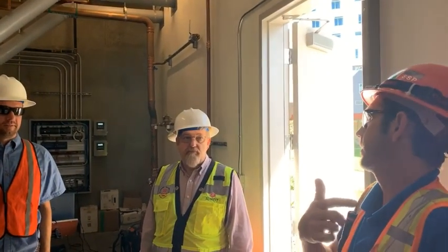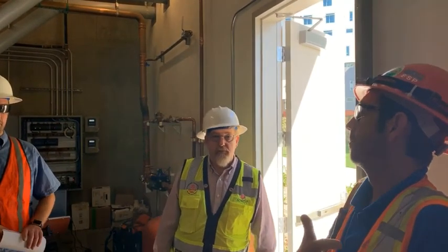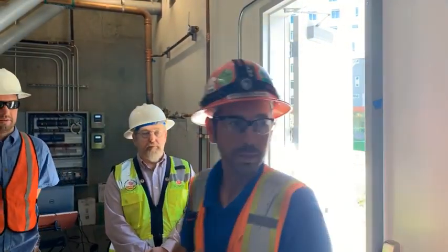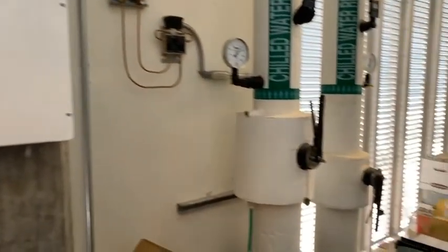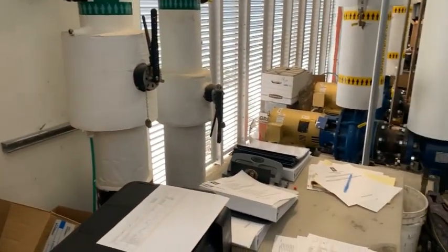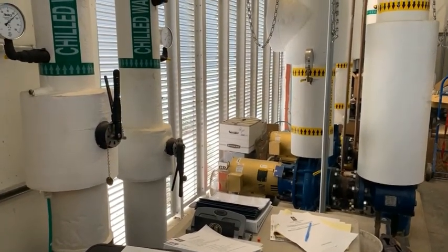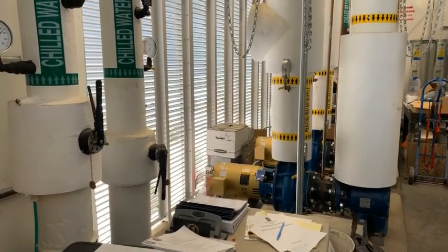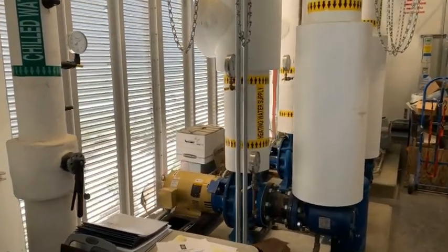Hydronic pumps, these pumps are the same as over there. 10 horsepower. Maintenance for these is pretty minimal. Yeah. There are greasable bearings on the motor. There's 2 Zerk fittings. What we can do is track runtime through the VFD. I'll show you guys that, and then you can grease for that.